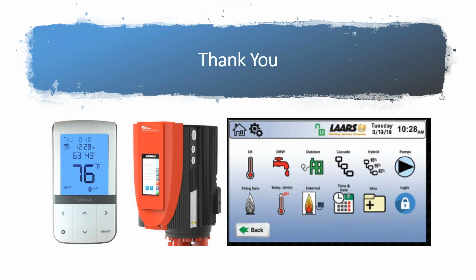So on the individual devices, if we use standard AA batteries, we'll get 2 seasons out of them, not 2 years, but 2 seasons. But there are options currently available on the actuators for the Danfoss valves to go out to an 8 to 10 year type battery. So there's a little bit of flexibility in there for you. It's not a one size fits all type thing.